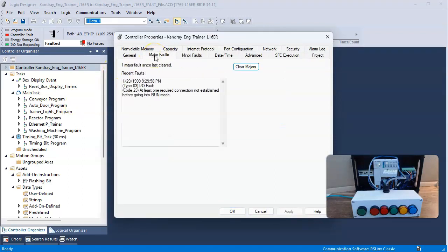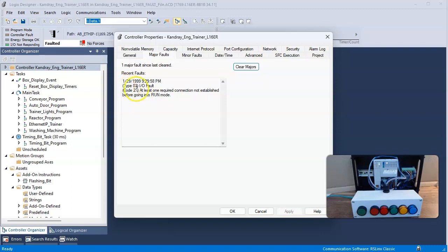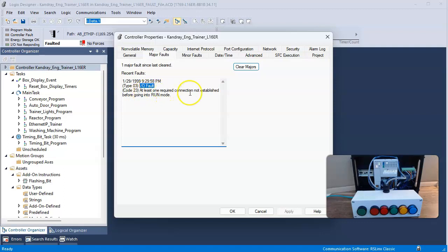So I click on major fault, and I do have a major fault. And it says type is 03, which is an IO fault. So I have a situation with my IO, and it's telling me it's code 23, which is at least one required connection not established before going into run. So at least I know it is with the IO.